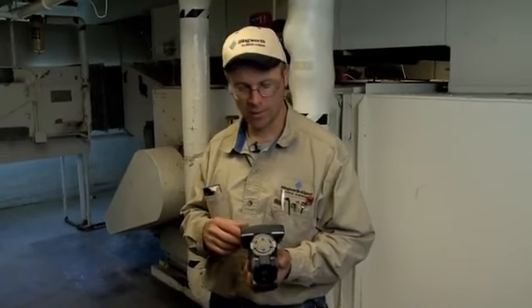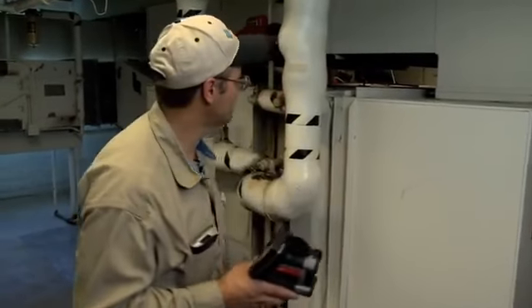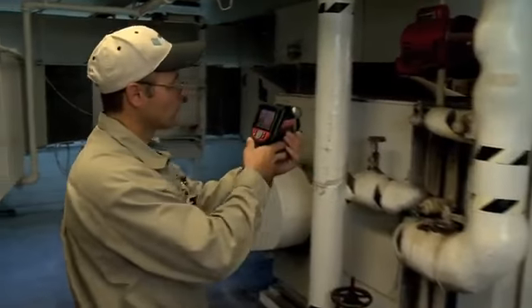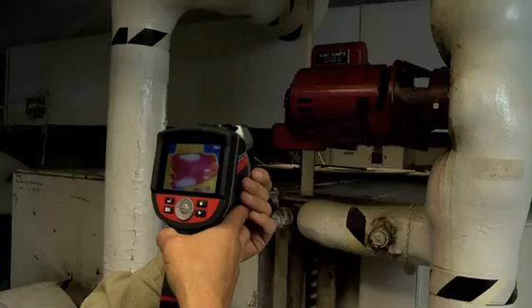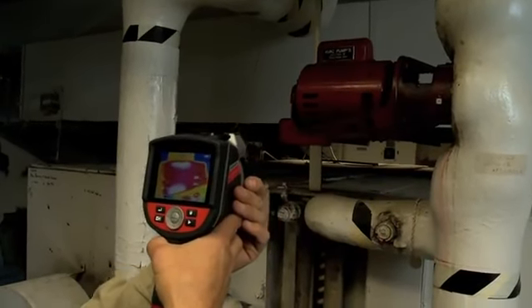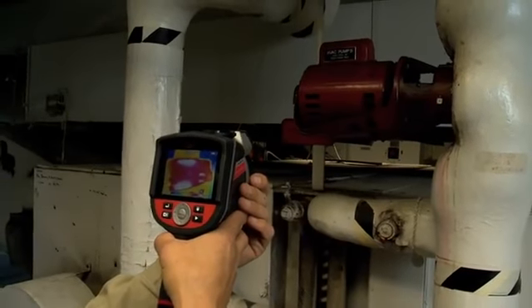It actually gives me a much broader look at the entire system than just using a thermometer or a temperature gun. With this item I can look at many things at once. I'm going to start over here. I can step back and I can focus in on the pump motor. I can check temperatures of the pump motor.